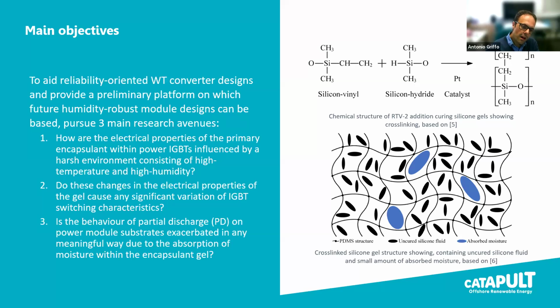And is there an effect on reliability, in particular on partial discharge and partial discharge inception voltage in power modules due to the absorption of humidity into the silicone gel? Silicon gel, as I said, is a polymeric chain, but when it's cured, it might contain imperfections, it might contain voids, and can trap moisture and other contaminants. And therefore we were interested in understanding how this affects the reliability and how it interacts with the standard substrate used in power electronics converters. Next, please.